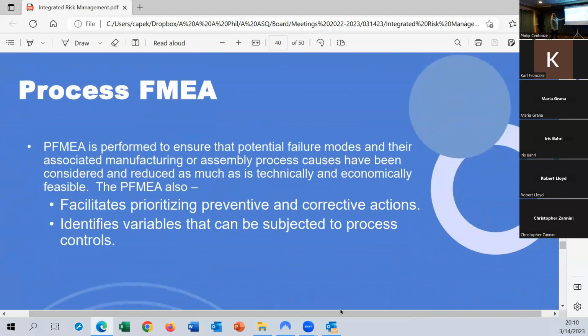And then the process FMEA, that's in the manufacturing process, where we want to see what the process can do to impact the device that we're manufacturing. There are things like sterility, for example. If it's a device that needs to be sterile, sterility can't really be checked. We can put things in the process to ensure that the sterilizer works properly, but there are no tests for that. If we didn't sterilize it properly, then our device could cause infection or things like that. So we want to look at every step in the process and determine how it can impact the operation of the device.